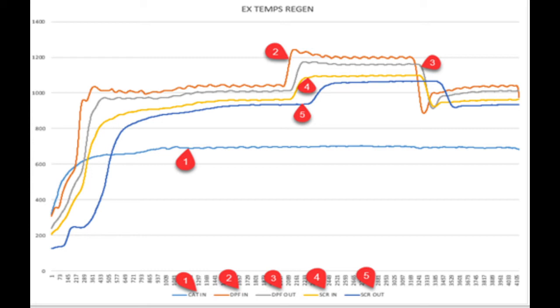Notice that about three-quarters of the way through, the temperature jumps up to 1,200 degrees. Only the 2250 does this — the 2350 will not do this; it will do the whole regen at about a thousand. This is the first thing that I do when I start to diagnose a problem with after-treatment: I do a stationary regen for about 30 to 40 minutes and I look at these temperatures. From what I see, I get a pretty good idea of what we need to do and where we need to go.